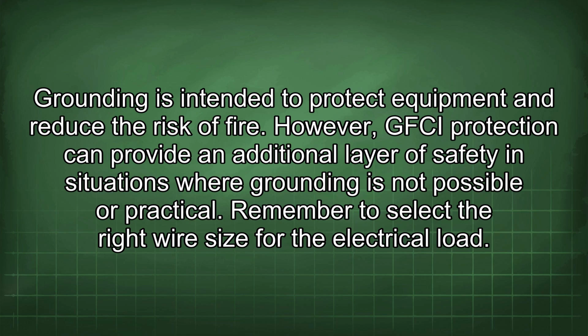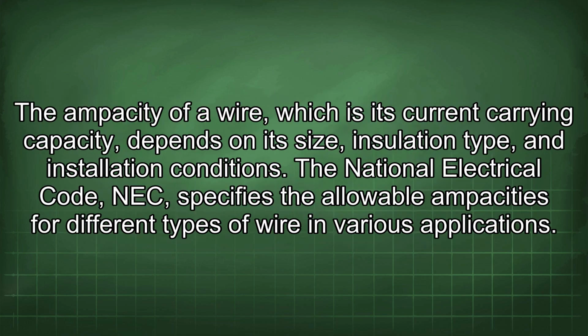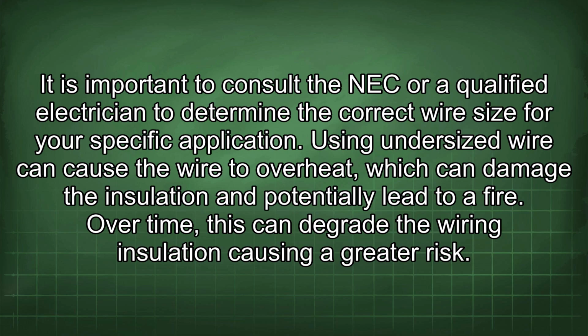Remember to select the right wire size for the electrical load. The ampacity of a wire, which is its current carrying capacity, depends on its size, insulation type, and installation conditions. The National Electrical Code, NEC, specifies the allowable ampacities for different types of wire in various applications. It is important to consult the NEC or a qualified electrician to determine the correct wire size for your specific application. Using undersized wire can cause the wire to overheat, which can damage the insulation and potentially lead to a fire. Over time, this can degrade the wiring insulation, causing a greater risk.